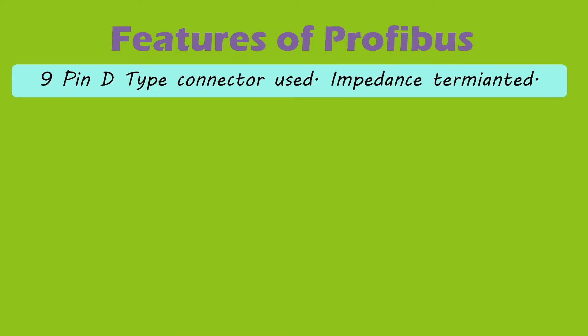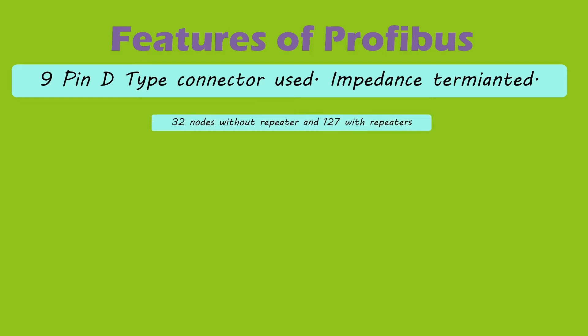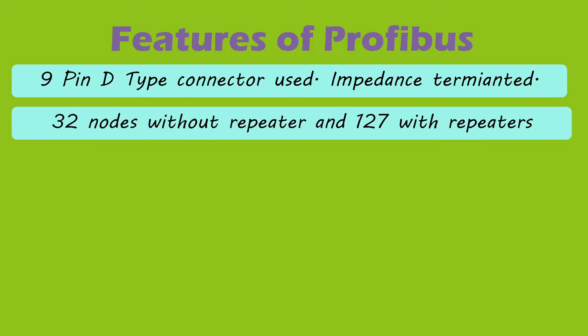Looking at the features of Profibus: Profibus uses a 9-pin D-type connector, which is impedance terminated at the ends. The number of nodes that could be connected on a single Profibus network is 32 without repeaters and 127 with repeaters.